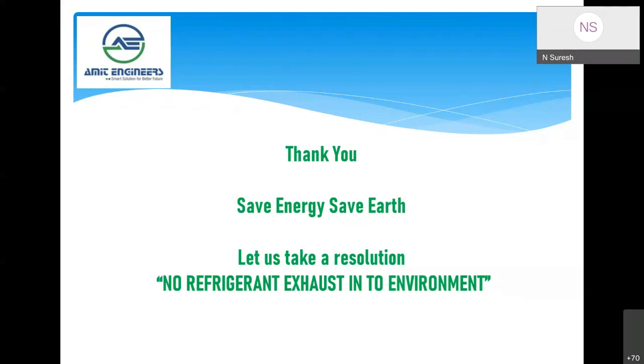For example, if we need to change only the filter drier, we can recover the refrigerant. In any workshop, if even 1 unit per month has its gas recycled, that is nearly 7 to 8 kg. Indian Railway is a big ocean, so in many locations, per year, even per month, if 10 units leave the refrigerant outside, it is going to harm the environment and, in turn, us. So we will try not to leave this refrigerant in the environment, and try to recycle or recover the refrigerants.